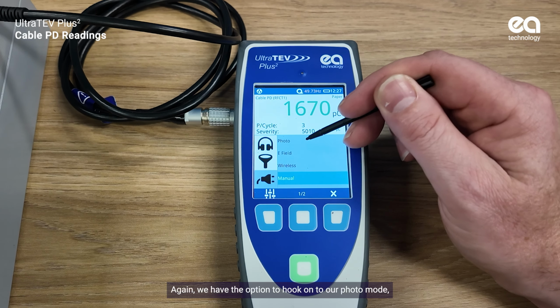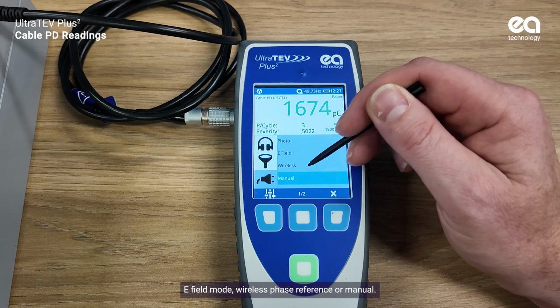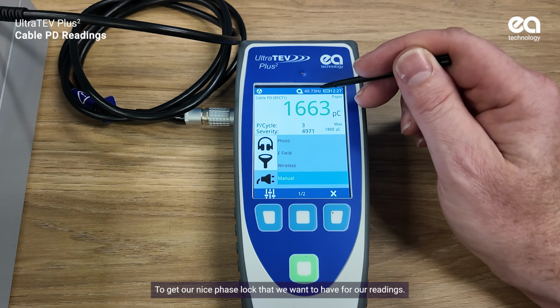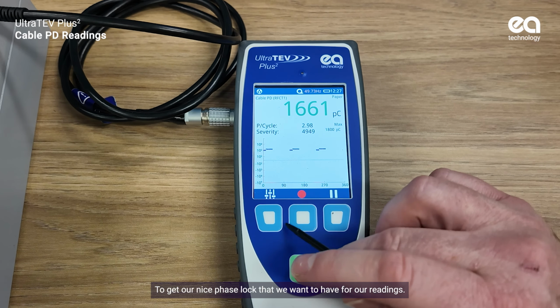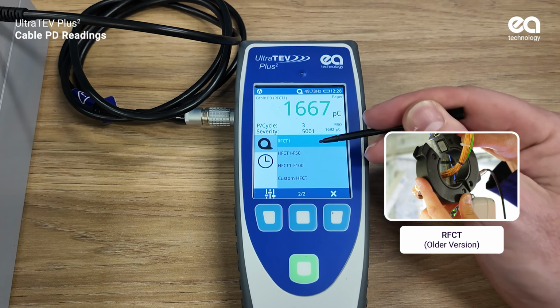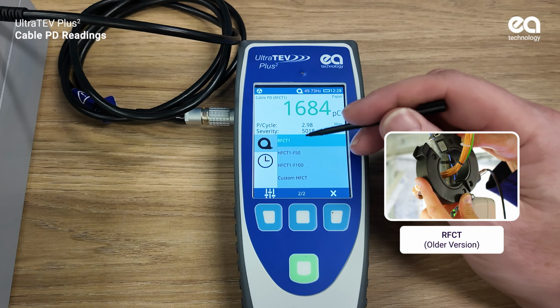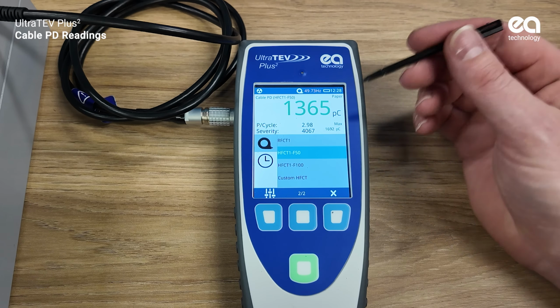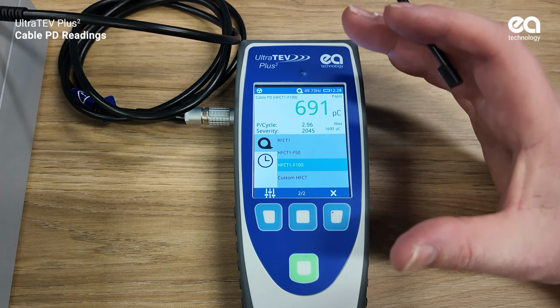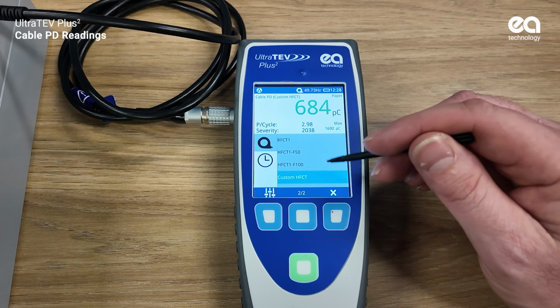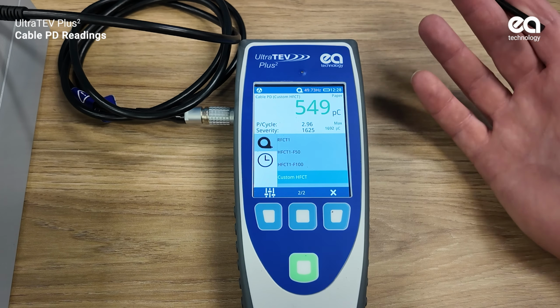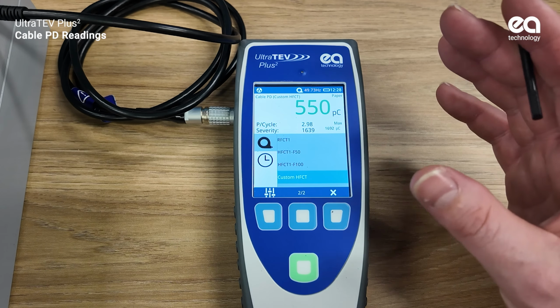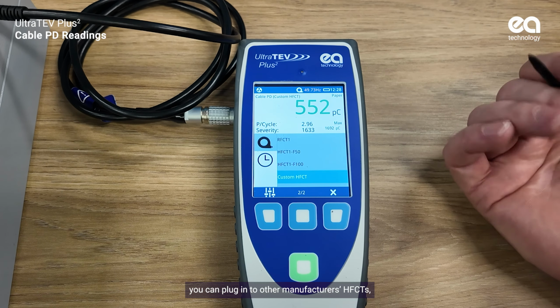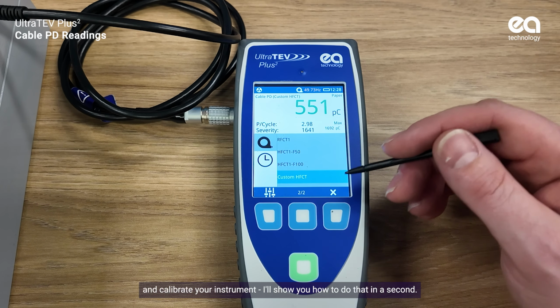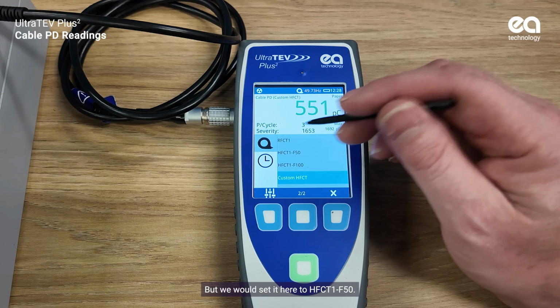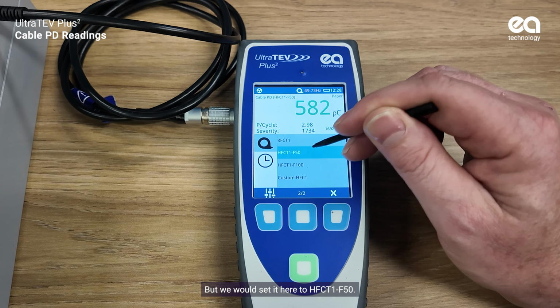Again, we have the option to hook onto our photo mode, e-field mode, wireless phase reference or manual to get our nice phase lock that we want to have for our readings. So if I click on the settings button again, it gives me this option here to choose a different HFCT. So I've got HFCT1, HFCT 50, HFCT 100, which is the bigger one. And then you've got that custom HFCT. That's where you can plug into other manufacturers' HFCTs basically and calibrate your instrument to that. I'll show you how to do that in a sec, but we would set it here to HFCT 50.